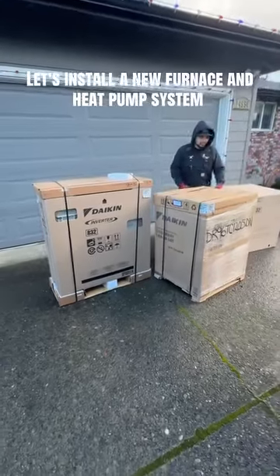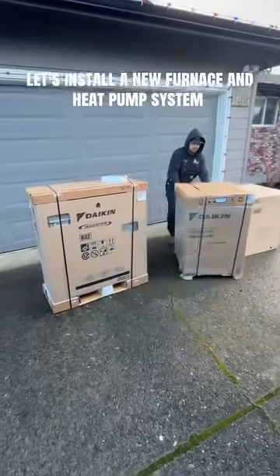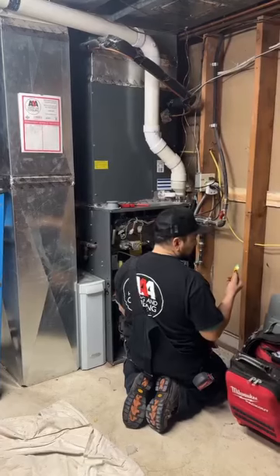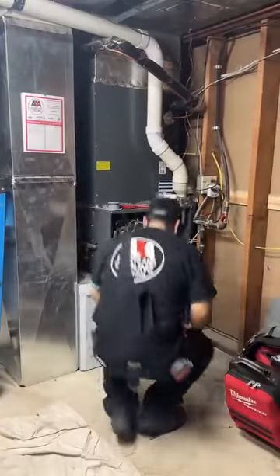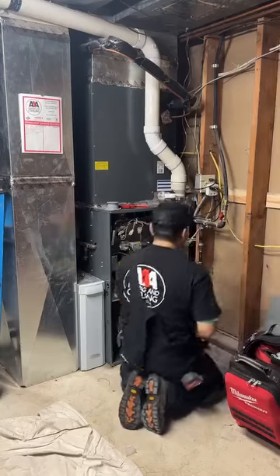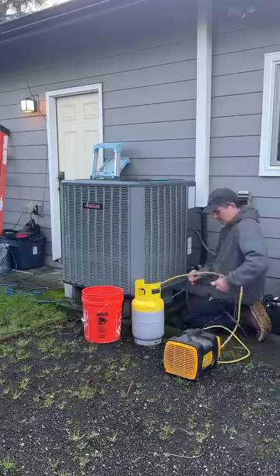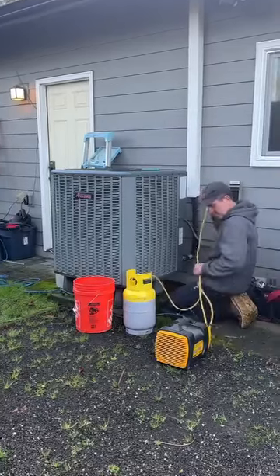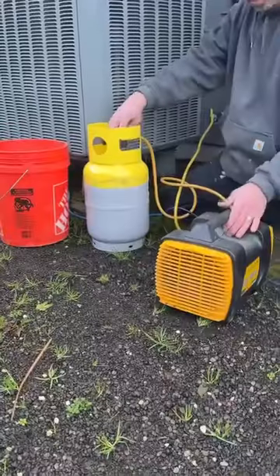Come along with us to install a new furnace and heat pump system at this customer's home. First, we verify power has been disconnected at the breaker. From here, we can disconnect the high voltage, low voltage, gas, drain, and exhaust. At the same time, we recover any remaining refrigerant still in the outdoor heat pump system.